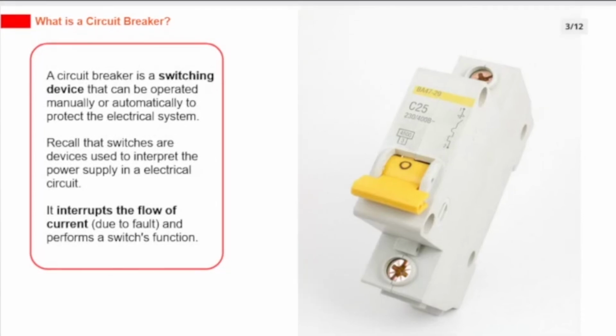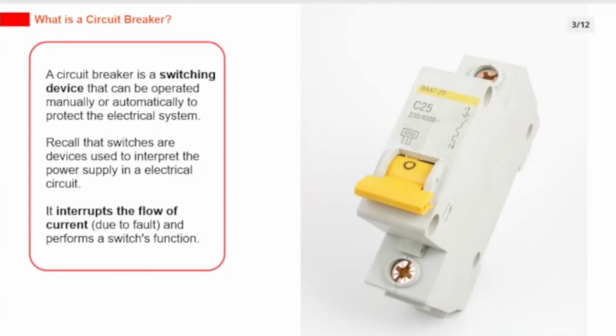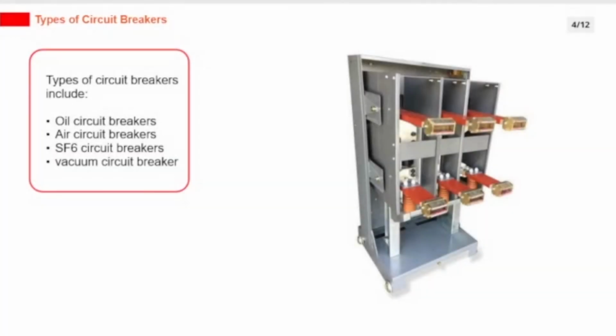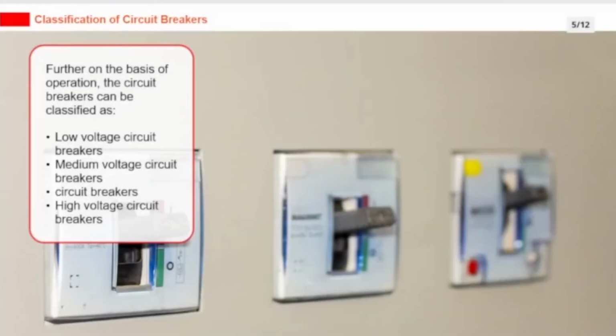A circuit breaker is a switching device that can be operated manually or automatically to protect the electrical system. Recall that switches are devices used to interrupt the power supply in an electrical circuit. It interrupts the flow of current, due to fault, and performs a switch's function. Types of circuit breakers include oil circuit breakers, air circuit breakers, SF6 circuit breakers, vacuum circuit breakers. Further on the basis of operation, the circuit breakers can be classified as low voltage circuit breakers, medium voltage circuit breakers, high voltage circuit breakers.